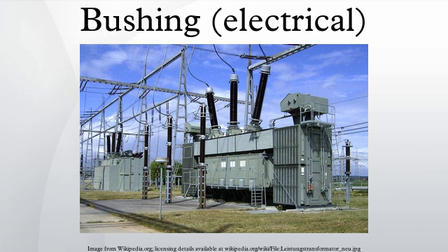A typical bushing design has a conductor surrounded by insulation, except for the terminal ends. In the case of a busbar, the conductor terminals will support the busbar in its location. In the case of a bushing, a fixing device will also be attached to the insulation to hold it in its location. Usually, the fixing point is integral or surrounds the insulation over part of the insulated surface. The insulated material between the fixing point and the conductor is the most highly stressed area.